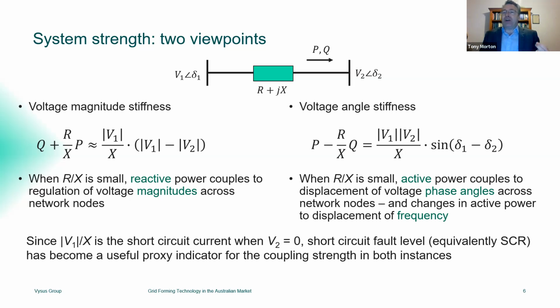And then this quantity V1 on X that appears in both of these formulae as a scaling factor, well, of course, this is simply, if we imagine that we have a low resistance and we just set V2 equal to 0, and we look at the current flowing, V1 on X is just the short circuit current that obtains if we put a short circuit at one end of this branch and look at the current delivered from the other end. So that's what underlies the use of short circuit currents and short circuit ratios as proxy indicators for strength, because it feeds directly into the proportionality constants in the stiffness formulae.